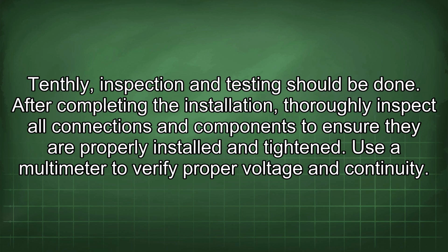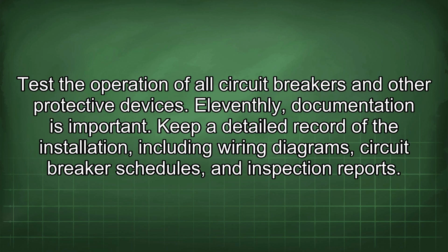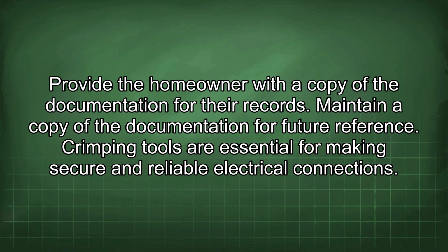Use a multimeter to verify proper voltage and continuity. Test the operation of all circuit breakers and other protective devices. Eleventh, documentation is important. Keep a detailed record of the installation, including wiring diagrams, circuit breaker schedules, and inspection reports. Provide the homeowner with a copy of the documentation for their records. Maintain a copy of the documentation for future reference.